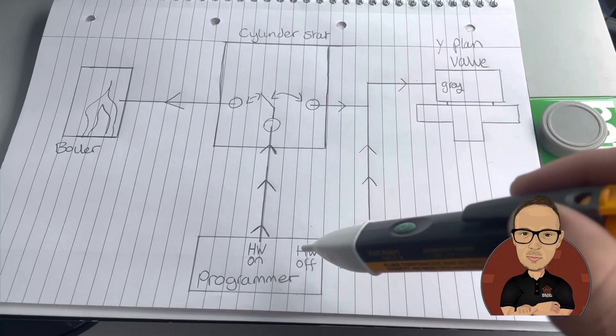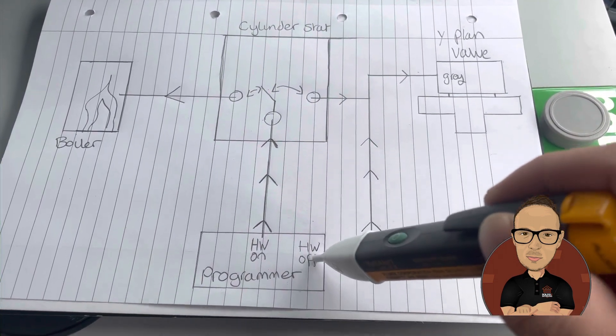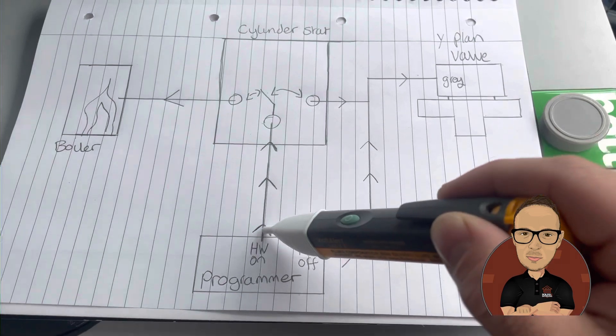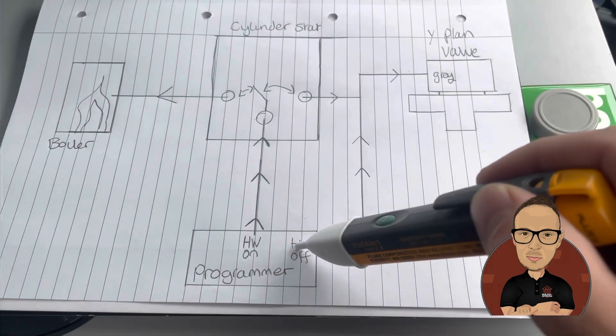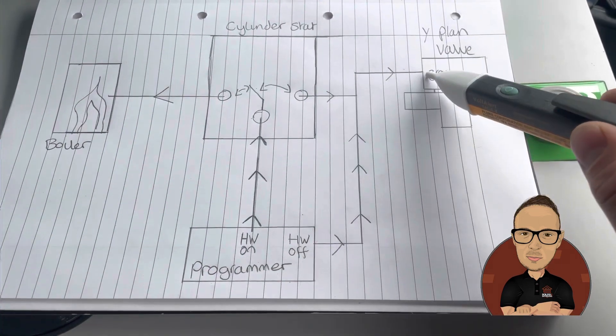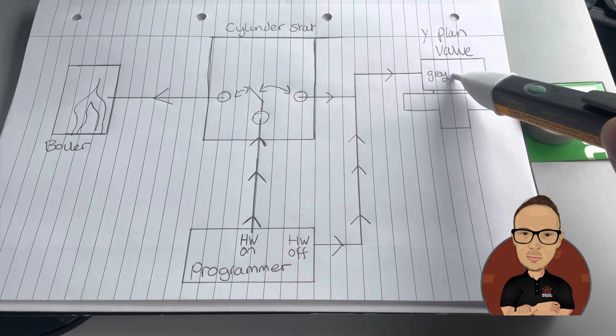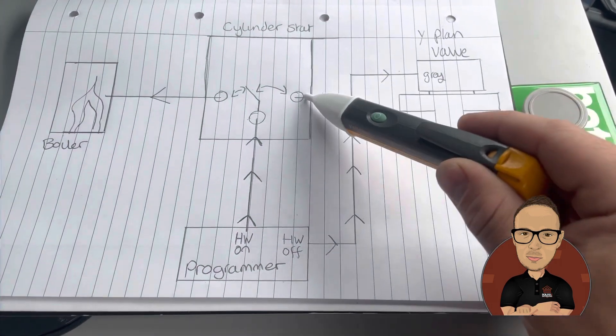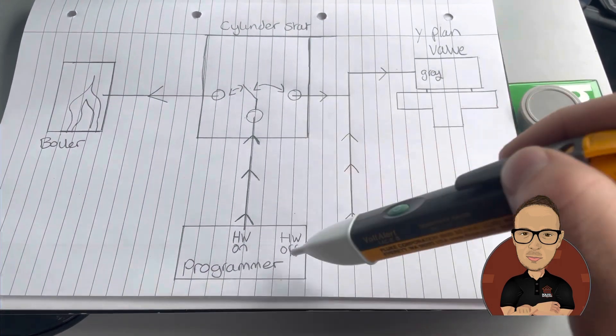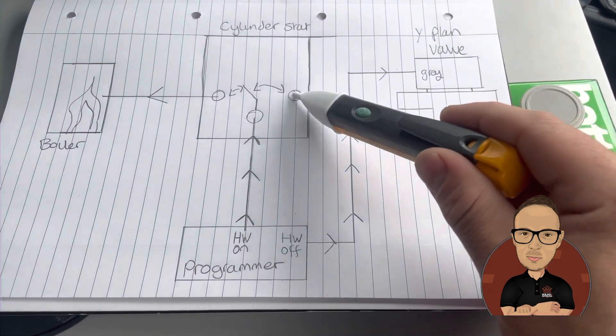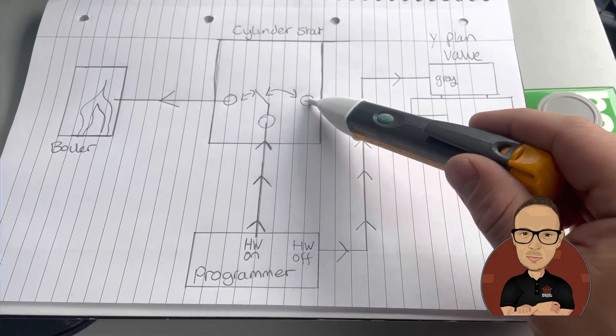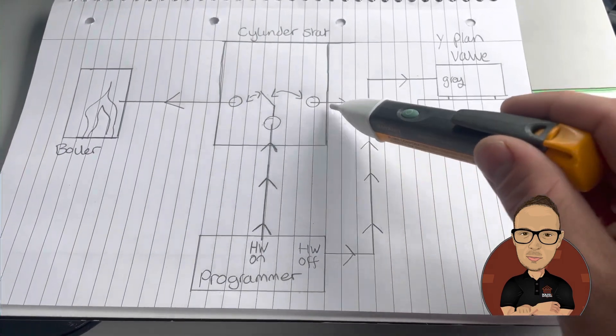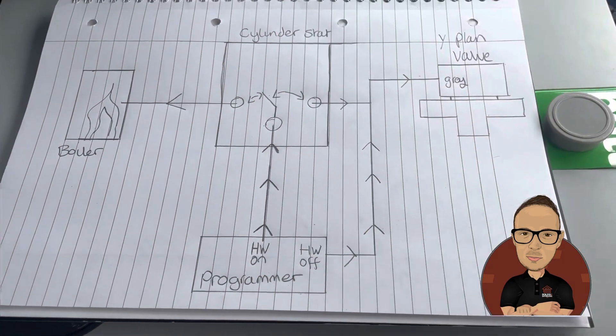However, if you click hot water off on the programmer, it now stops sending power up there. So it sends it this way, which goes to your grey on your Y-Plan valve. And that's why when hot water is off, you still get power to your cylinder stat. And I think that's why some people find it a little bit confusing.